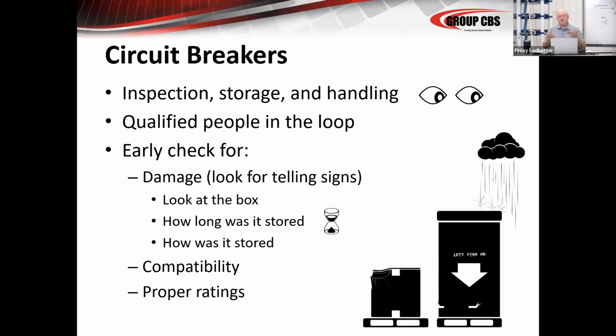Lots of times, and particularly in low voltage switchgear, some of the low voltage breakers may have 4-wire ground fault. So if they have 4-wire ground fault, they will have a different sensor and a secondary in the back that feeds the ground fault current into the trip device. You can't just put any 800 amp breaker in any 800 amp cell. So you have to make sure the compatibility is right. I've seen jobs where customers inserted 800 and 1600 amp breakers that were set with 4-wire ground into cubicles that were not equipped for 4-wire ground. Therefore, that means they didn't have the ground fault protection in the proper cells. Those sorts of things are the things you have to look for.